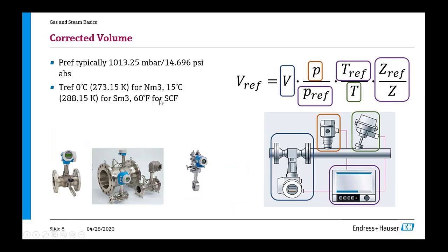Corrected volume. Typically, if you measure gas in a combined cycle power plant, you will want to measure that gas in normal meters cubed, standard meters cubed, or standard cubic feet. And this corrected volume is actually a mass term. You take the actual volume measurement, and then you have to compensate it. You have to multiply it with the relation of operating pressure to reference pressure. Reference pressure is typically 1013.25 millibar or 14.696 psi, times the relation of temperature at reference conditions.